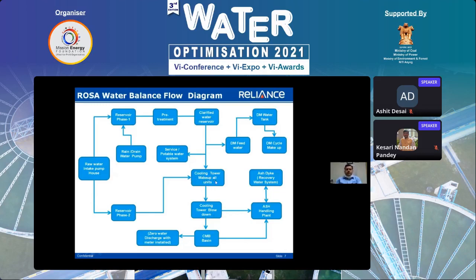Likewise, from the cooling tower blow down, we have optimized our blow down. It is going to the ash handling, where we have the recovery water system, and the water is coming back from the recovery water system. We have 6 recovery water pumps there. All the ash water going to the dike, we are extracting from that, and that water is coming back to our plant for further utilization. So that's how we complete the cycle and maintain zero water discharge of the plant.